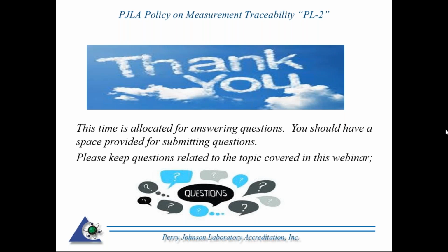If you have a good system of intermediate checks, you put something in place right where it came back, then you could cut that down significantly. If you have a good system where you could detect perhaps it started shifting here, or if it's showing everything is stable through your system of intermediate checks, then maybe you just have to go back and look at the last time that you ran that intermediate check. But yes, the answer to your question is yes, that can be used, and I used to do it myself as far as capturing data for repeatability.